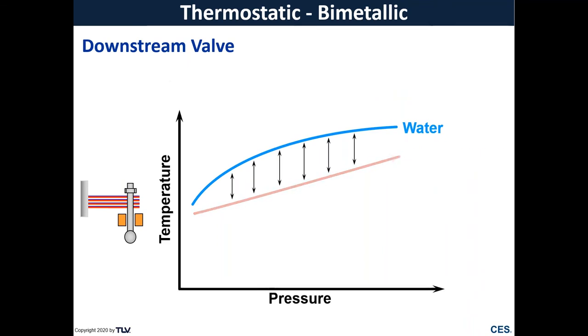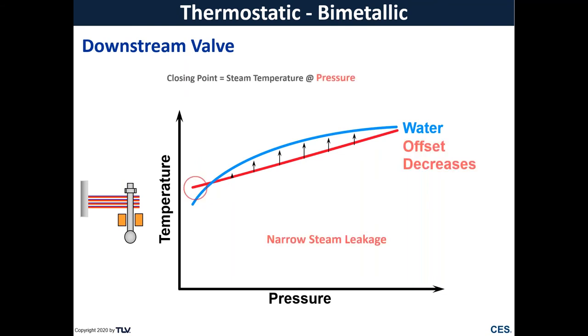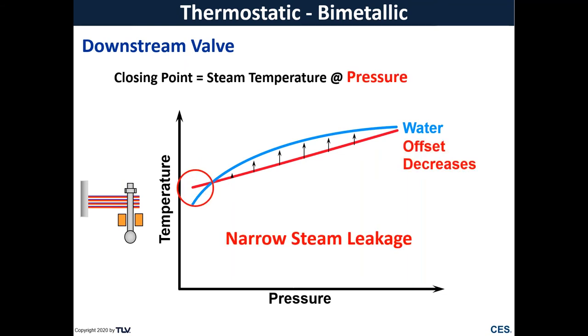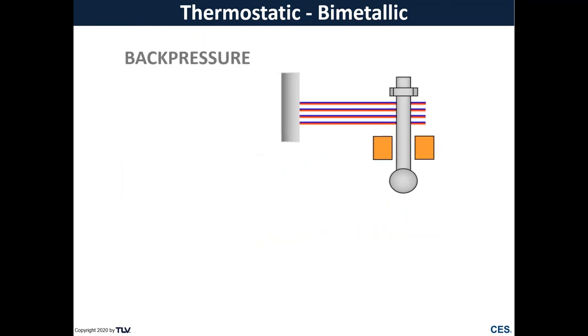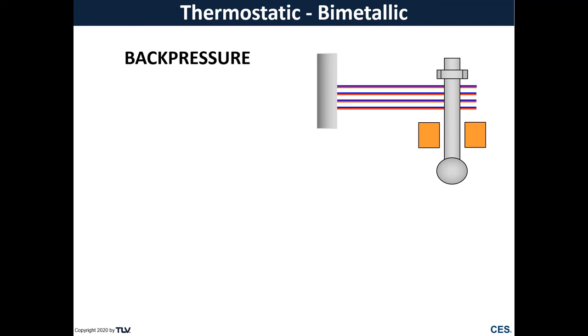Since those bimetals are having to undergo a lot of strength just to pull back against the upstream pressure, those bimetals can start to become fatigued and they start losing some of their strength. And so that requires a higher temperature under the same pressure. So what this can cause is you get a closing temperature that's equal or even higher than your steam temperature. That will result in a leaking steam trap.